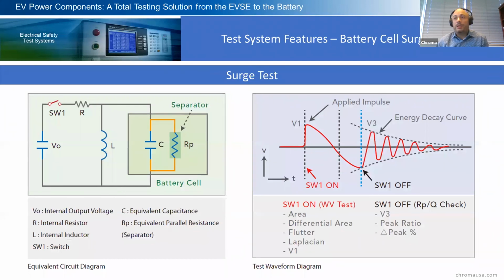Now for the battery surge tester. The surge test applies a non-destructive, short-period, low-energy impulse voltage on a lead acid battery cell, right? Typically, when you do a high pot test, it's considered a destructive test because it wears down the insulation every time you apply it. So if you do high pot 5-6 times on a product, most likely it's going to fail at some point. In this case, we're just applying a quick surge test, which is a low-energy pulse.